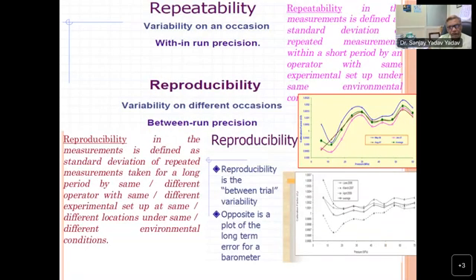So, if you see this particular pressure gauge graph, you will see the repeated measurement over the years and the behavior of the gauge. So, you can also check the average. Over the years, you can find the behavior of the gauge is the same, but there is a little bit away. So, that is the drift in the measurement.